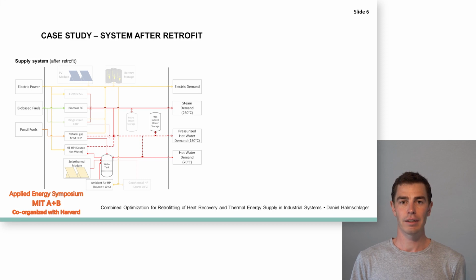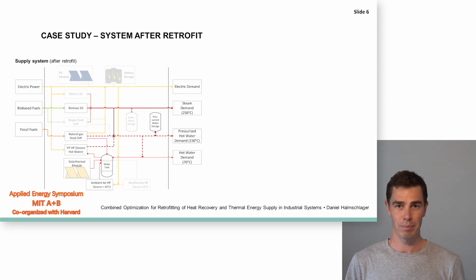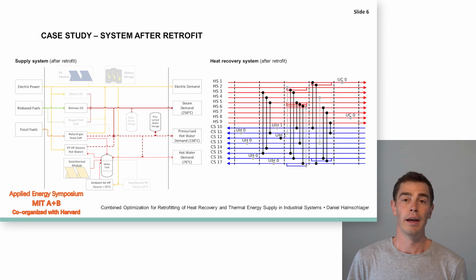And I will now jump directly to the solution and give you a little bit of data on the model itself afterwards. Out of the supply options, the solver selected a biomass steam generator, a high temperature heat pump, an ambient air heat pump, a large area of solar thermal modules and storages on the low and medium temperature levels, additionally to the pre-existing natural gas-fired CHP plant. The optimal new heat recovery system consists of 13 new direct heat exchangers and 1 new utility heat exchanger. 8 of the previously existing heat exchangers are reused and shown in the chart in gray.